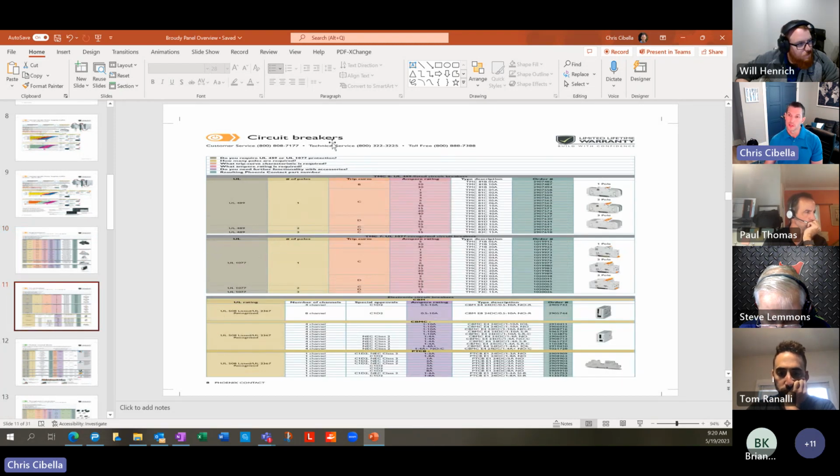All right, so still sticking with circuit protection here, or moving over to circuit protection. With circuit breakers, we have a couple different flavors. These top ones here are what we call UL 489 breakers. They're easily identifiable as they have these little finger guards on them. And then below them is our TMC 7 series, which are UL 1077. If you're not sure of the UL rating that's needed, UL 489 trumps 1077. They're only a couple dollars more. So I would go with the UL 489s.